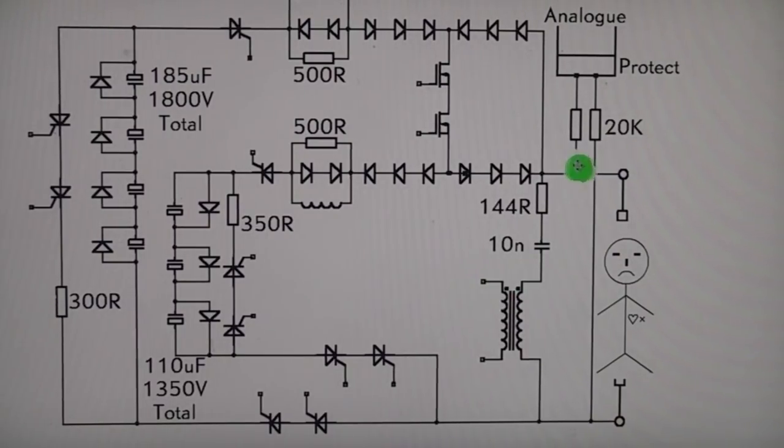I'm not sure whether this would actually have a low enough bandwidth to pass the main defibrillation pulse. The other thing it might be to do is to actually monitor the connections of the paddles. As we saw on the pack, the paddles are stuck together so that it can actually monitor the fact that they're in the pack, they haven't been opened. So it might be this just injects high frequency signal in here to monitor it either directly through the loading or possibly through the sensing circuitry. I'm not totally sure about that.